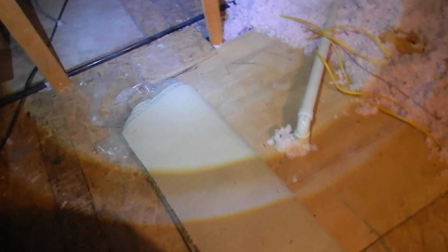So I come over here for heating. I'm coming around, and I got gas piping in the way. I don't want people stepping on my gas pipe. You want people stepping on your gas pipe? They should have put a curb across here, painted red. Some people call them gutters, so a trough. But something, okay, but we don't have anything. So people can be stepping on your gas pipe.